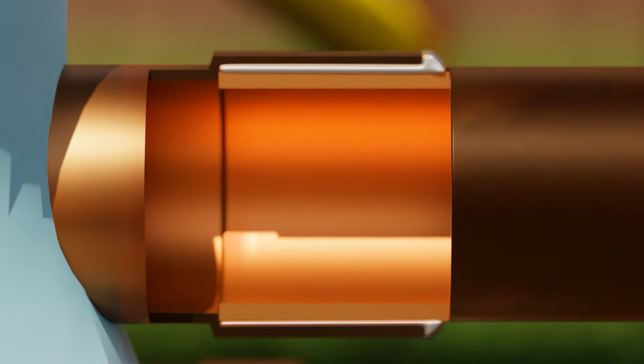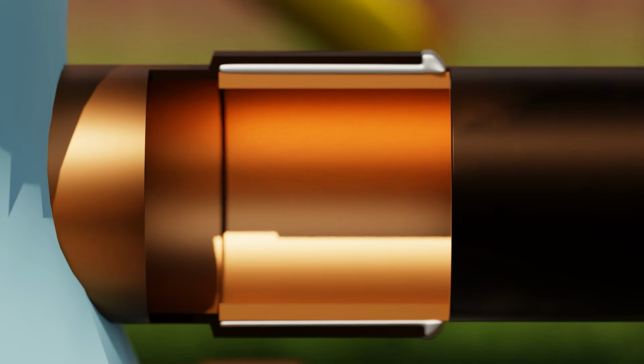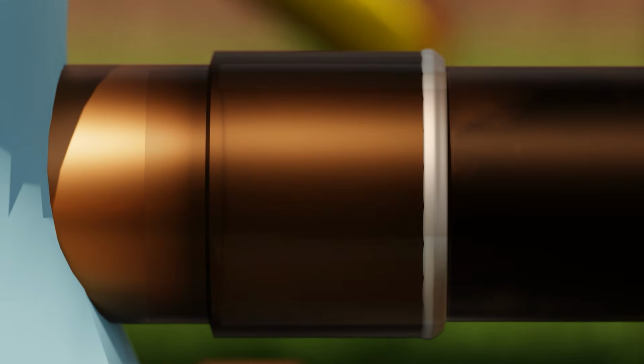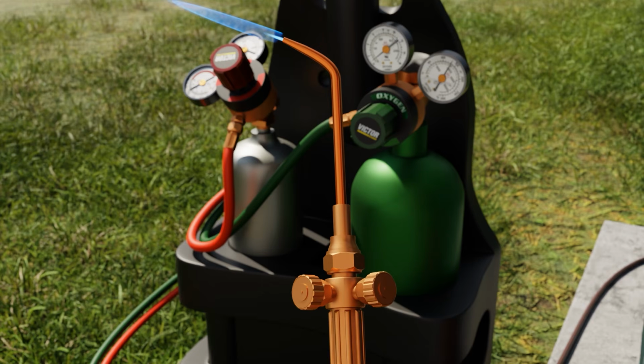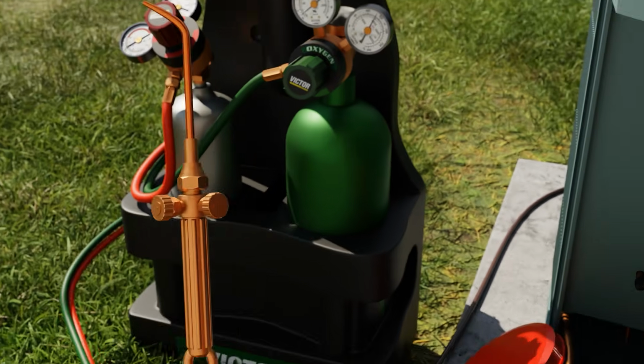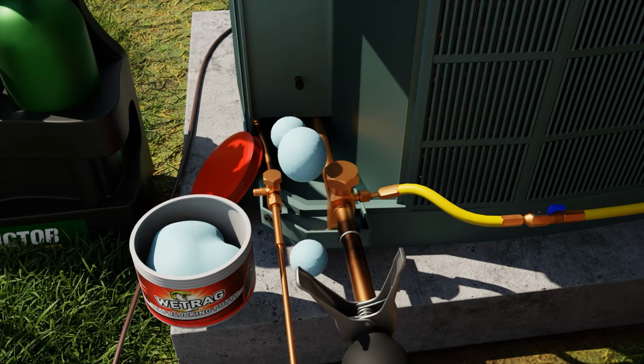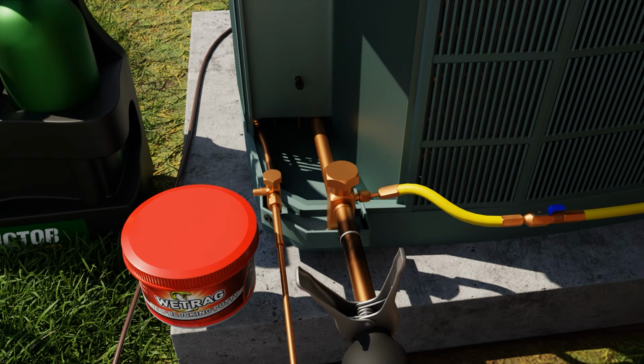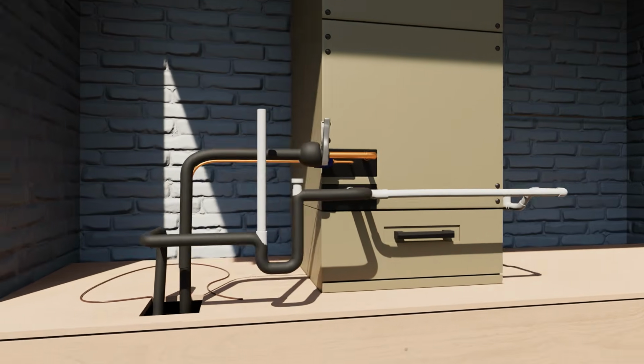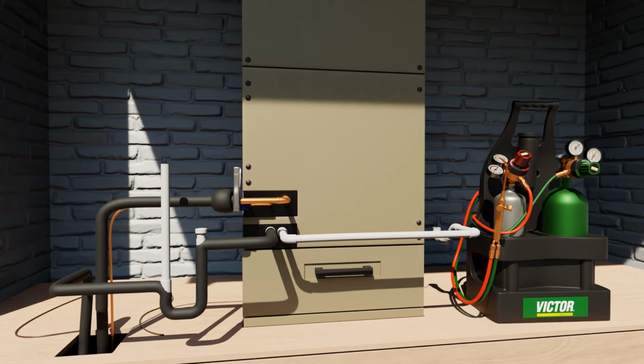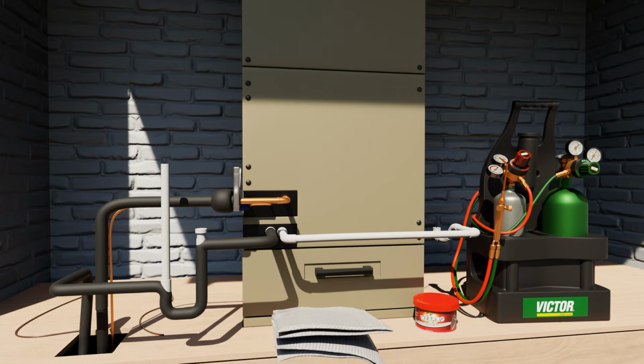Our goal is to get that entire joint hot enough to draw our solder in via capillary action as shown. Getting a good cap on the end is nice, but it's much more important that you get the joint to the right temperature so that you can pull the alloy into the joint. Next, we're showing moving to the inside to braze, but generally speaking, you'd do the inside first. Then you'd go outside and do the suction and liquid line at the same time. Here we're just going to continue showing the process, kind of following the flow of nitrogen through the system.